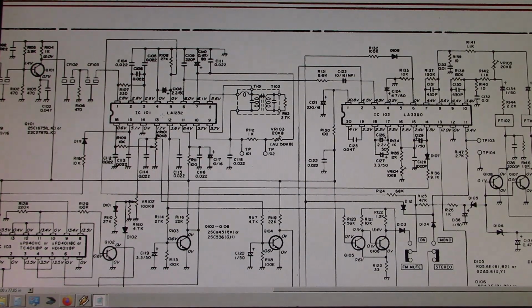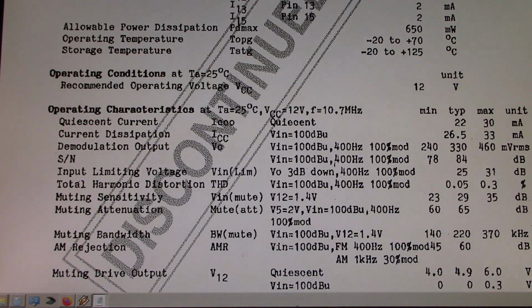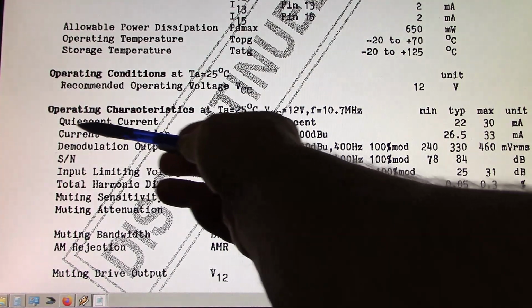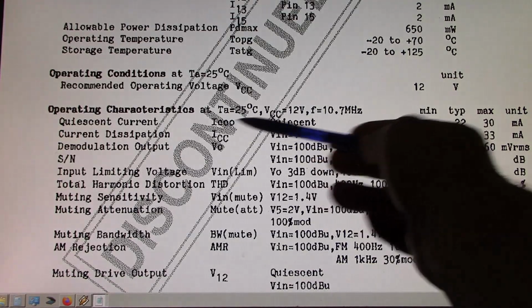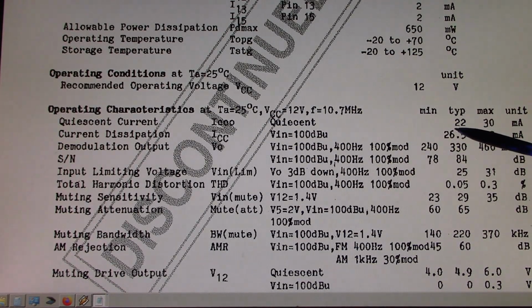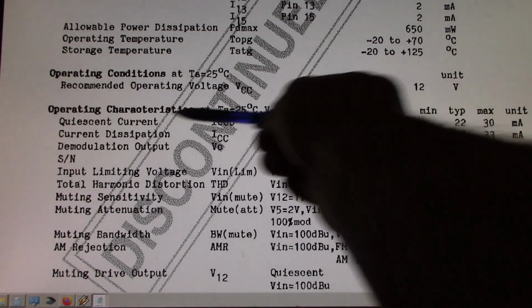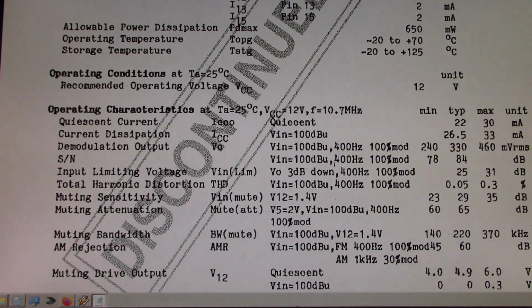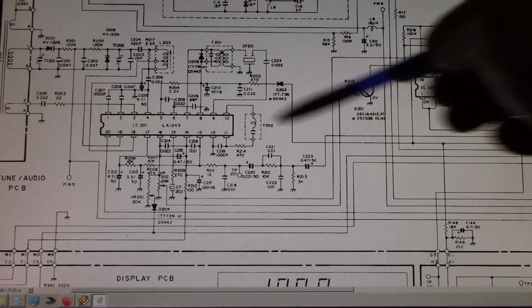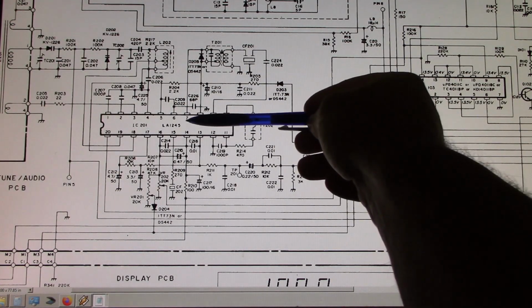If we look at the data sheet for the LA1232, so here again, if we look at the characteristics, we have quiescent current. ICC is typically 22 milliamps to 30 milliamps, and we're getting 21.3, so we're just a shade below typical. So I think that chip is okay. It's running correctly. It's not overheating. And same thing if I go to the AM chip, the LA1245.